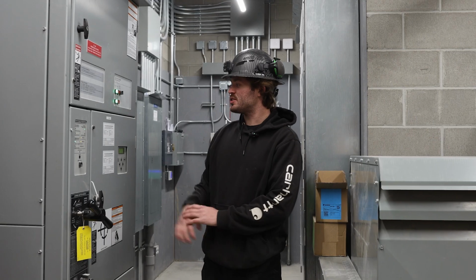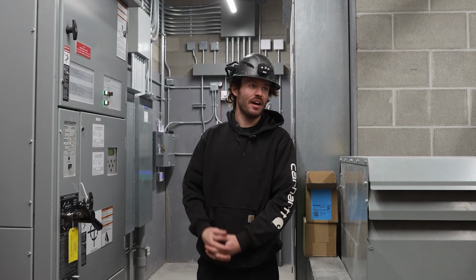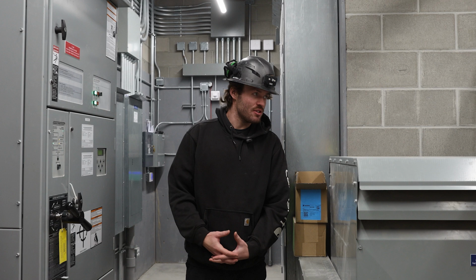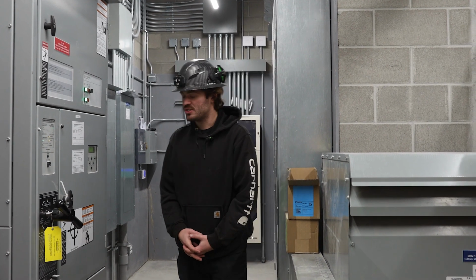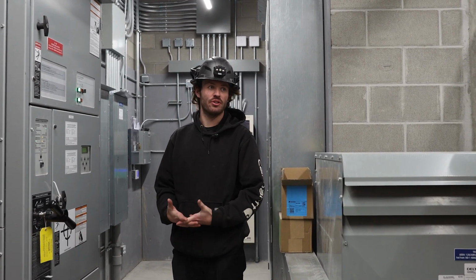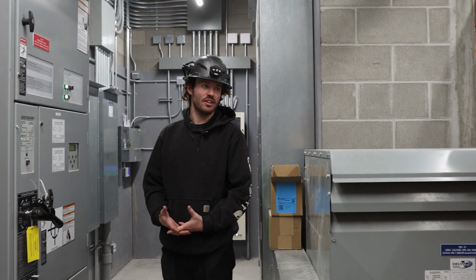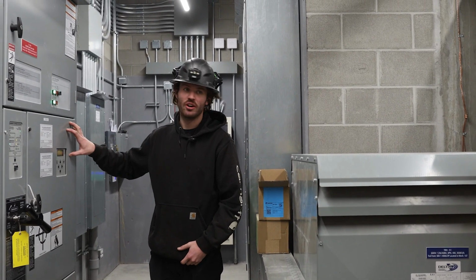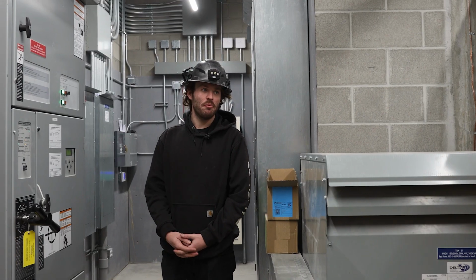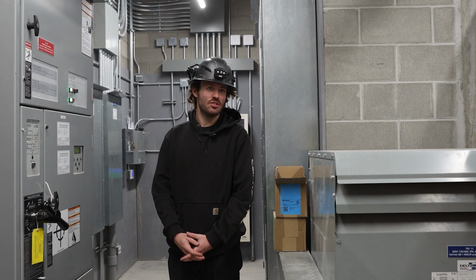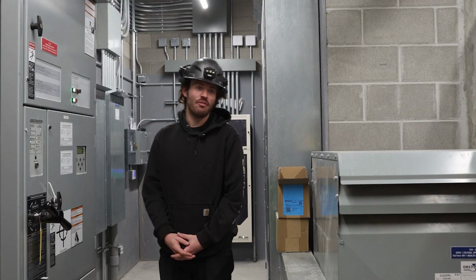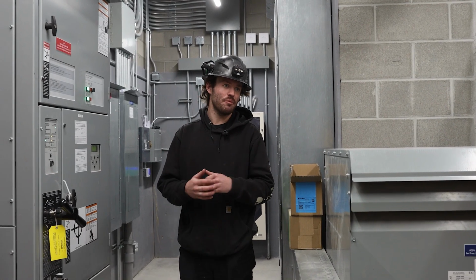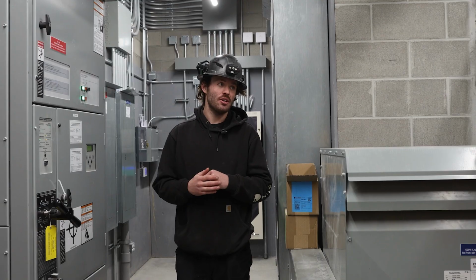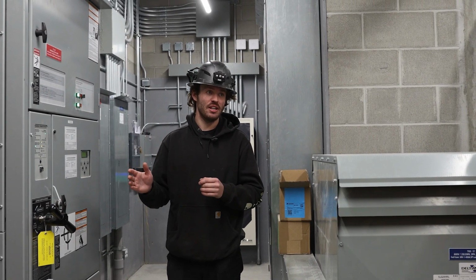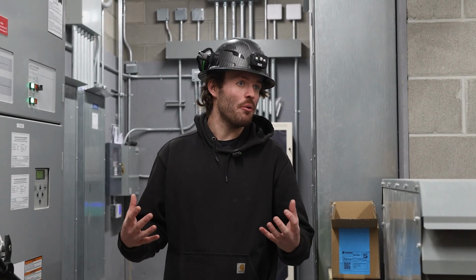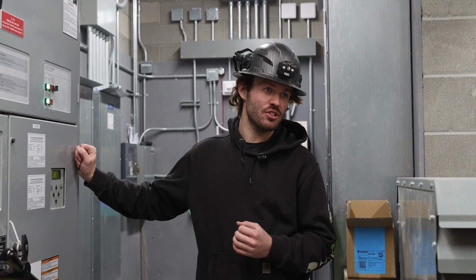They are human. This is the emergency transfer switch. We're currently in the mechanical room beside the back door to the building. This is the brains of the operation for the generator. Our generator is simply sitting there in automatic, waiting for this to tell it to start. The switch operates by monitoring our utility voltage at all times, so the incoming power to the building. If that voltage were to dip below a set point, increase above a set point, or the frequency decrease or increase, basically bad power, it's going to call the generator to start.